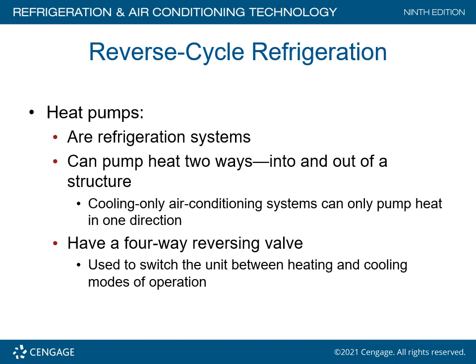Reverse cycle refrigeration. The best way to describe a heat pump is basically a refrigeration cycle operating in reverse. Heat pumps are refrigeration systems. They can pump the heat two ways, into and out of a structure. Cooling-only air conditioning systems can only pump heat in one direction. You must have a four-way reversing valve in order to make this happen. It is used to switch the unit between heating and cooling modes of operation.